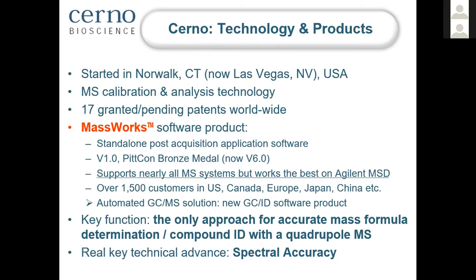We have now built a second generation product for fully automated analysis, the GCID, which you'll hear more about later. The key function of the MassWorks software is really the only approach for accurate mass analysis, and thereby to perform formula determination, elemental composition determination, and compound ID on a quadrupole system. But our real key contribution to the field, we felt, is something that's somewhat orthogonal to that, but it's an integral part of it. It's called the idea of spectral accuracy. I'd like to spend a couple minutes walking you through the idea of spectral accuracy, how it can be achieved, and how useful it can be in mass spec analysis.